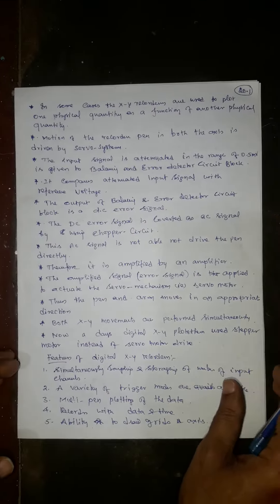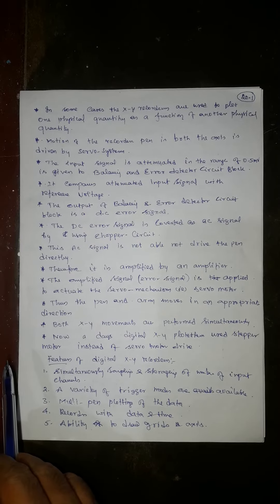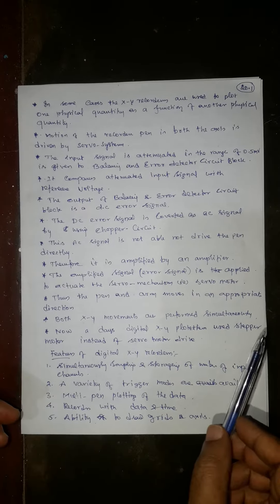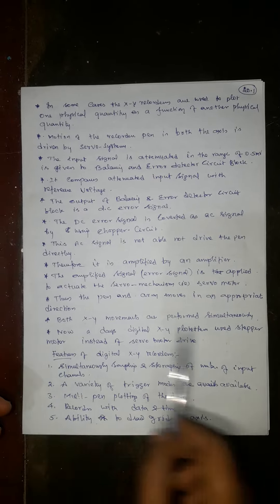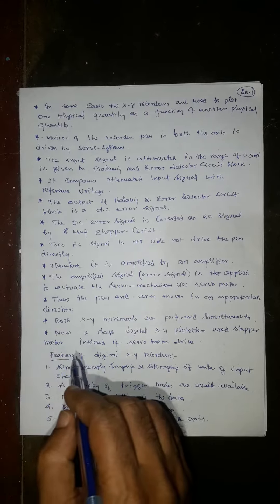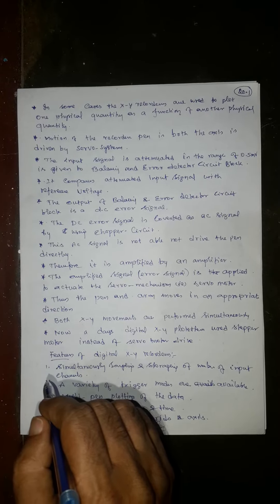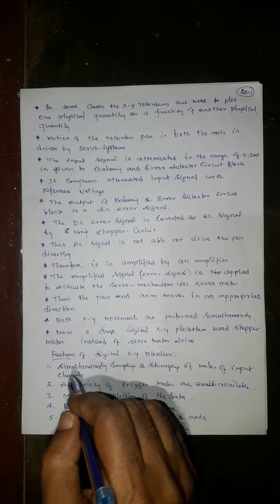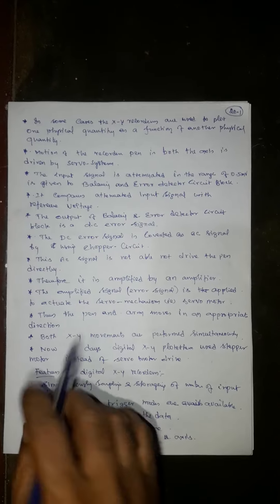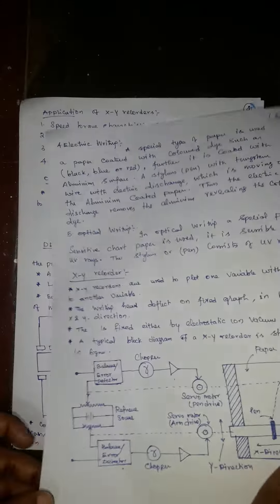XY recorders are used to plot one physical quantity as a function of another physical quantity. In the X axis, you can put one variable; in the Y direction, you can put another variable. The motion of the recorder pen in both axes is driven by a servo system or servo motor. The input signal is attenuated in the range of 0 to 5 millivolt and given to the balancing or error detector circuit.